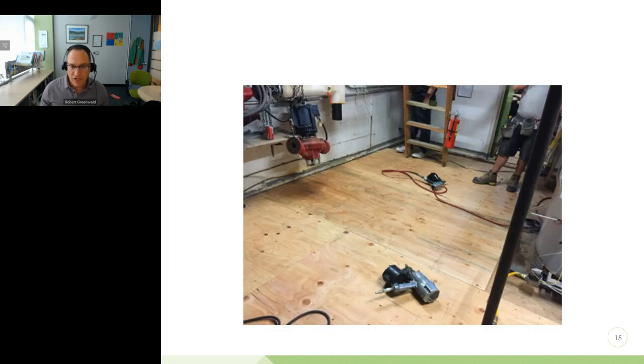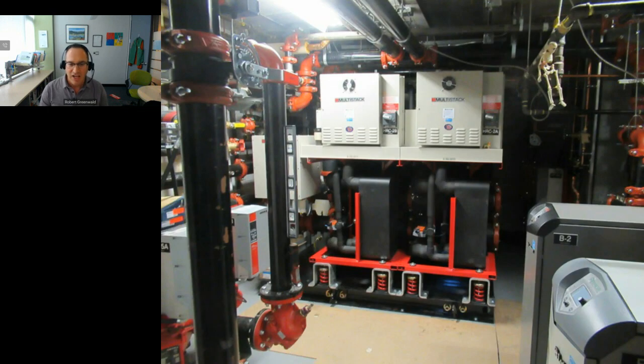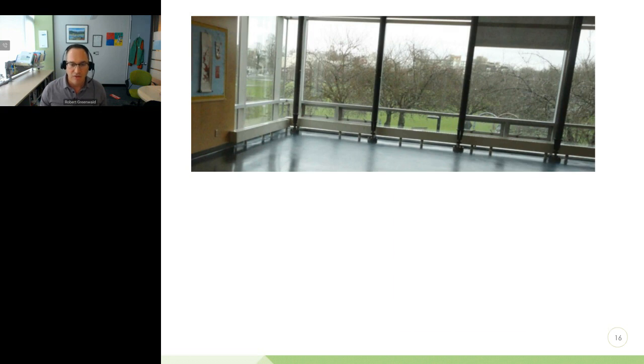In construction, the unique challenge of deep carbon retrofits compared to passive house new construction is the tight space available. Getting the heat recovery chiller into a confined space isn't easy, so using a modular chiller and managing issues like vibration are key. You can see the tight space in this photo, which also highlights the importance of thinking through zone-level issues.